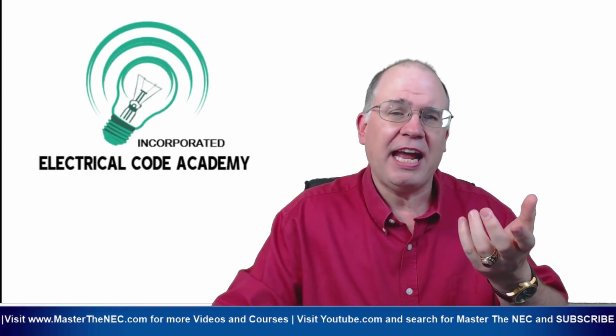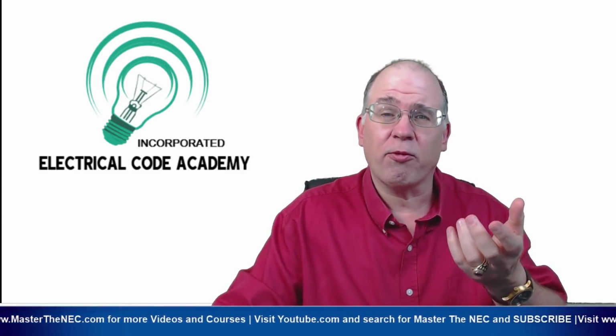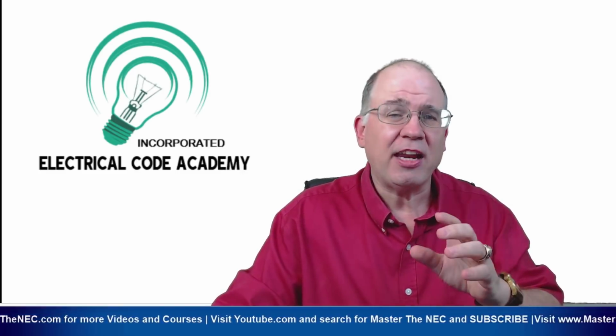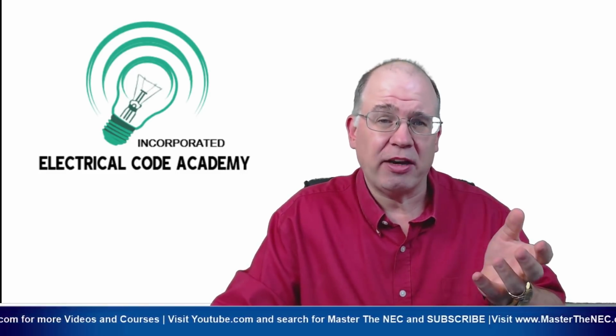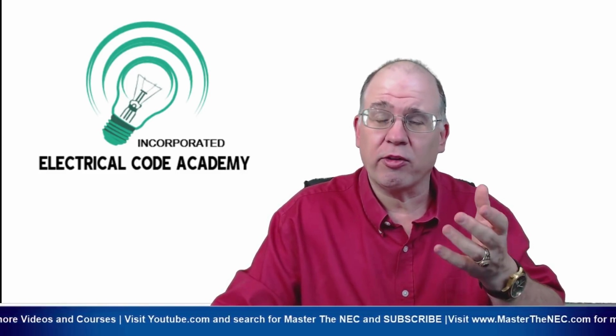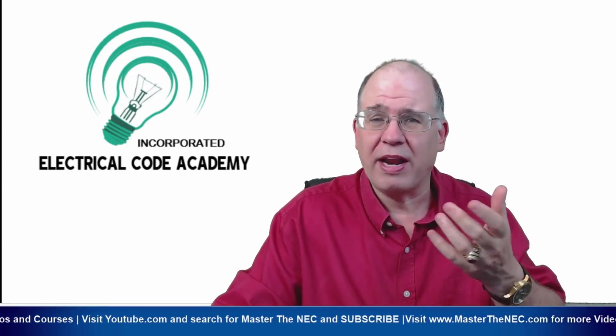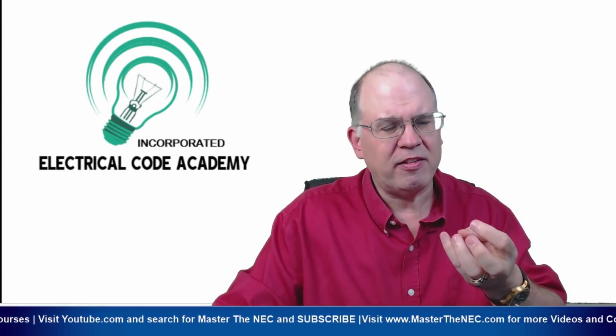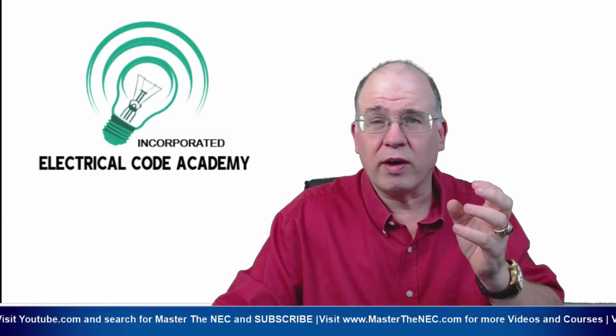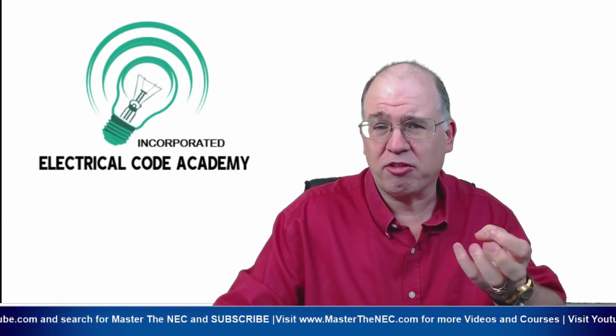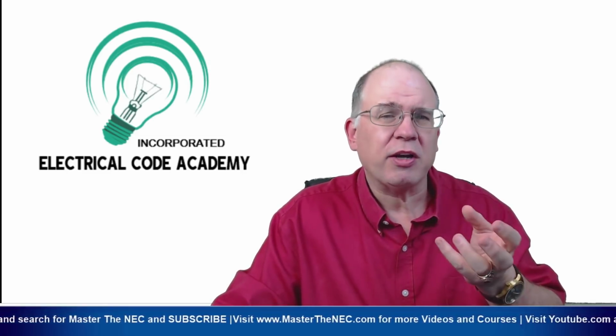As far as the bare, it's interesting enough. I do get people that ask me, what is the UL listing for bare copper? And that's not a UL, it's an ASTM standard. And that ASTM standard, whether it's B3 or B8 or what have you, discusses the soft drawn, hard drawn, whatever copper, and the number of strands. B8 covers all the stranding.